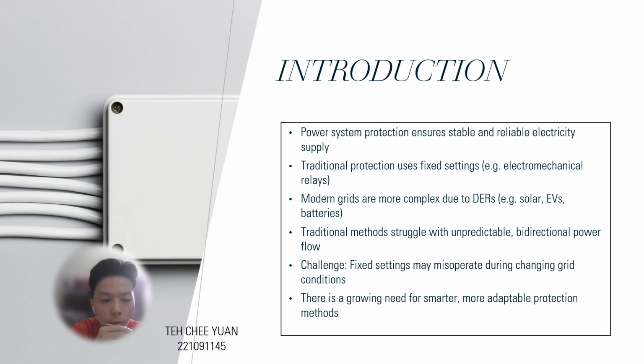They were built for one directional stable power flow, so now with all these dynamic changes, fixed settings may cause delay in tripping or even worse, fail to respond at all. This opens the door for new, smarter protection approaches, and that's where adaptive protection systems come in. Well, I will explain further in the next slide.